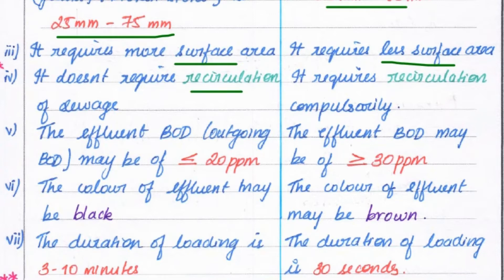The slow rate trickling filter does not require recirculation of sewage, but the fast rate trickling filter requires recirculation capacity. The effluent BOD in the slow rate trickling filter may be less than 20 ppm, but the effluent BOD may be more than 30 ppm in the fast rate trickling filter.